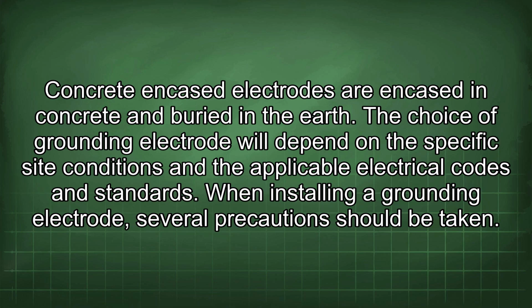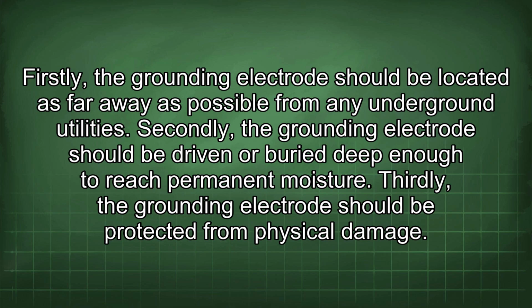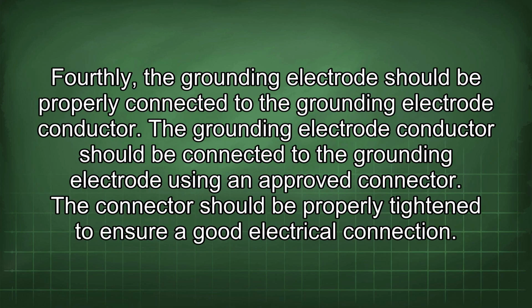When installing a grounding electrode, several precautions should be taken. Firstly, the grounding electrode should be located as far away as possible from any underground utilities. Secondly, the grounding electrode should be driven or buried deep enough to reach permanent moisture. Thirdly, the grounding electrode should be protected from physical damage. Fourthly, the grounding electrode should be properly connected to the grounding electrode conductor. The grounding electrode conductor should be connected to the grounding electrode using an approved connector. The connector should be properly tightened to ensure a good electrical connection.